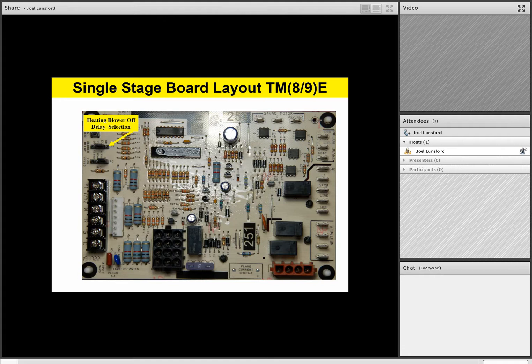Right above that is the last error button. That last error button allows you to retrieve flash codes. It should be noted that the control board will remember the last 5 errors. If it has 5 errors or faults on the board, it will remember the last 5. If there's more than 5, it just kind of rolls off on the end. It just remembers the last 5 errors on the board.